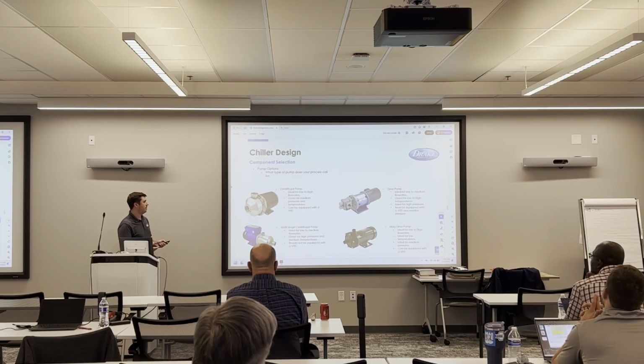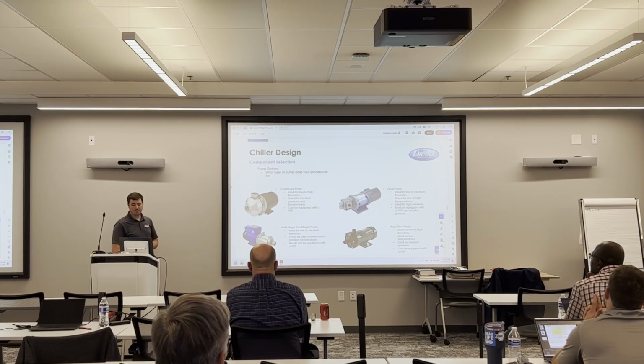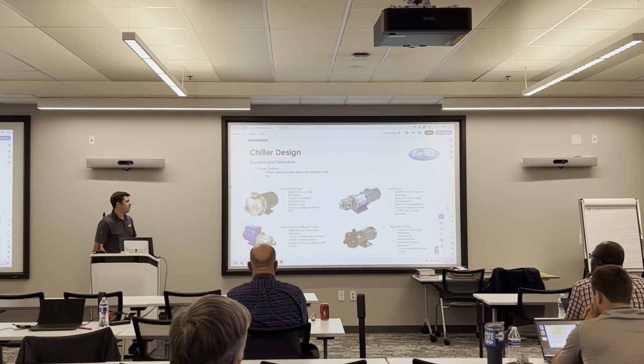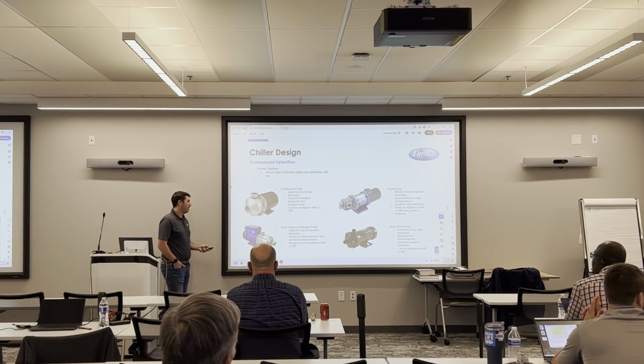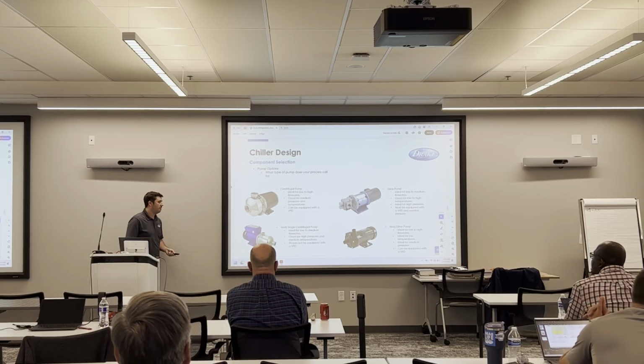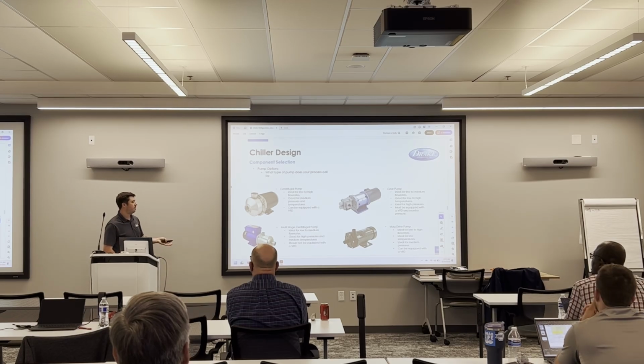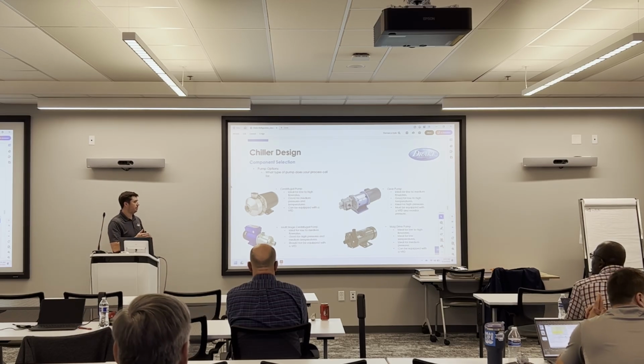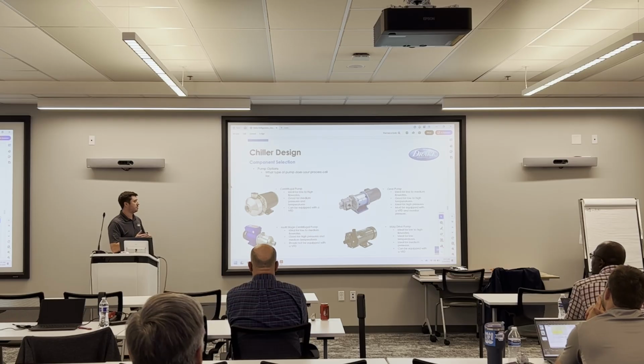And again, that's good for medium pressures. So if you need something for a higher pressure application, we generally recommend a multi-stage centrifugal pump. Ideal for low to medium flow rates, good for high pressures and medium temperatures. Don't recommend equipping this type of pump with a VFD. If you put a VFD on this type of motor, you're not going to yield the high pressure that you're looking for.